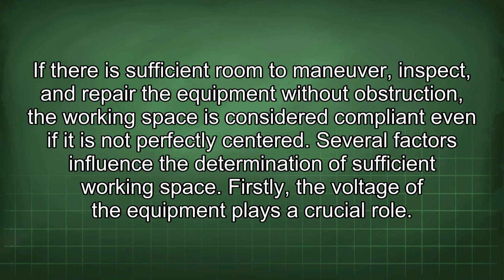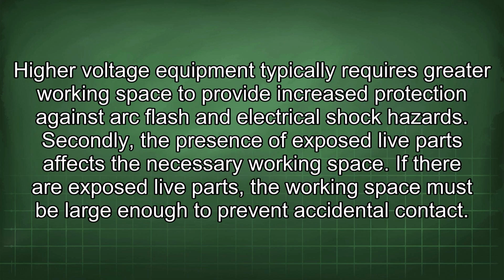Several factors influence the determination of sufficient working space. Firstly, the voltage of the equipment plays a crucial role. Higher voltage equipment typically requires greater working space to provide increased protection against arc flash and electrical shock hazards. Secondly, the presence of exposed live parts affects the necessary working space. If there are exposed live parts, the working space must be large enough to prevent accidental contact.